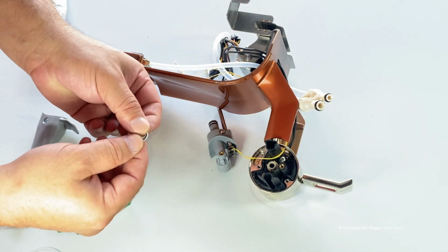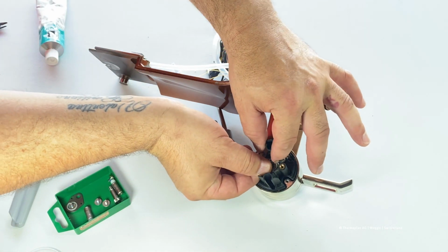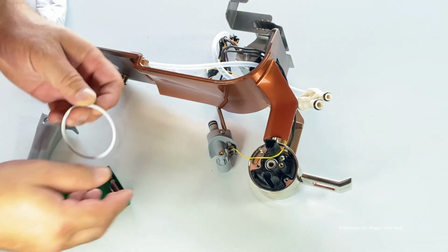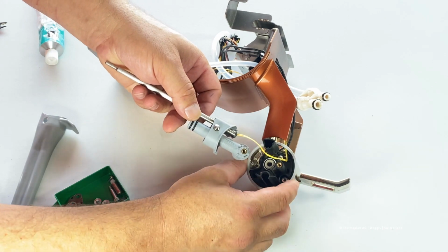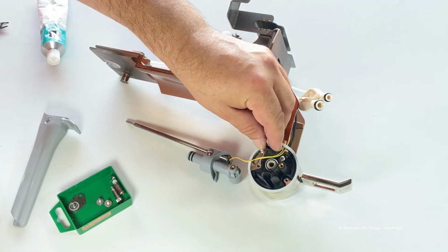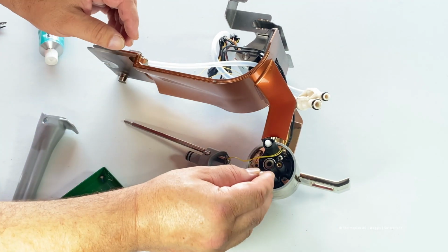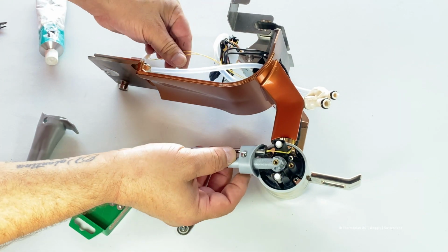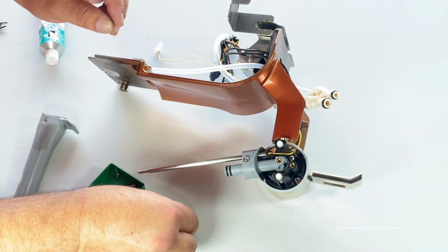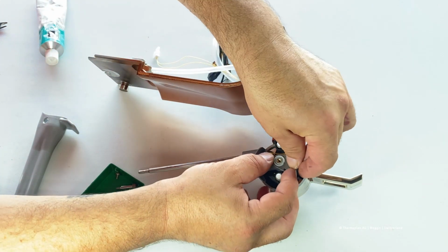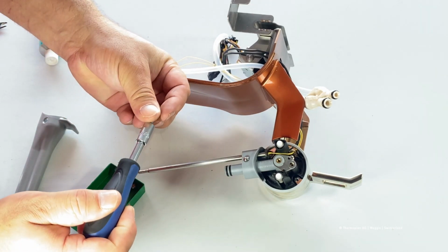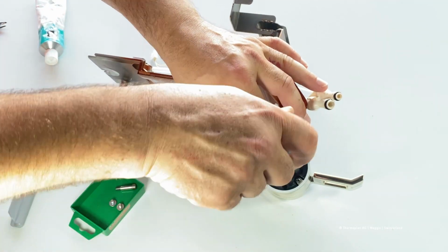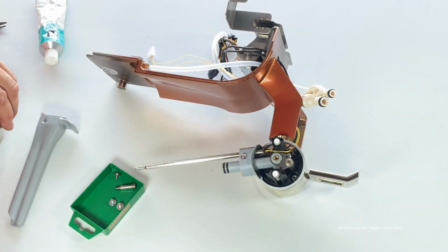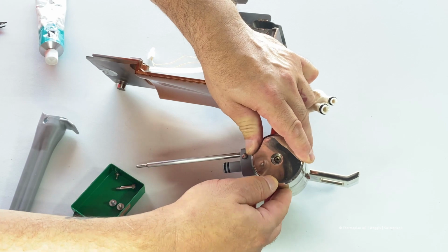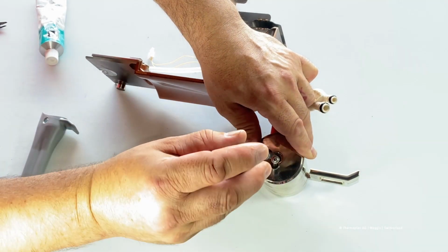Then I put the seal on the shaft. Also important, the direction. Then I put the Teflon bearing ring back, the two springs. Then I attach the steam connection piece and the little support plate with the screw. And finally I put the cap back on with its screw.